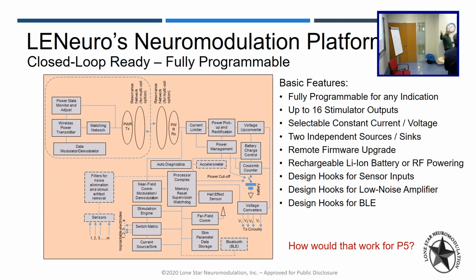But the output is 16, but input is how many? Processor has multiple inputs. You tell me and I can expand it. But then the original input signal conditioning or analysis? As it stands, it does not have any inputs. It's basically pre-programmed. So you program it through the wireless controller. You say, I'm just making this up, I want to apply 4.3 milliamps between electrode 1 and 5. Here's the amplitude, here's the pulse rate. So it's programmable on the stimulation side, but there's no limit. You can program it for any other thing.